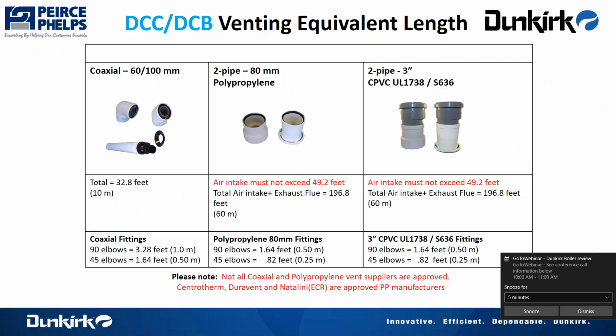If we're going to 2-pipe polypropylene, note that you must use both your vent pipe and your incoming pipe must be polypropylene. And we have a total, the air intake can't exceed just under 50 feet, and total air intake and exhaust cannot exceed together 196 feet. You see your friction on the elbows is a whole lot less. 90-degree elbows are 1.64 feet, 45-degree elbows 0.82 feet.